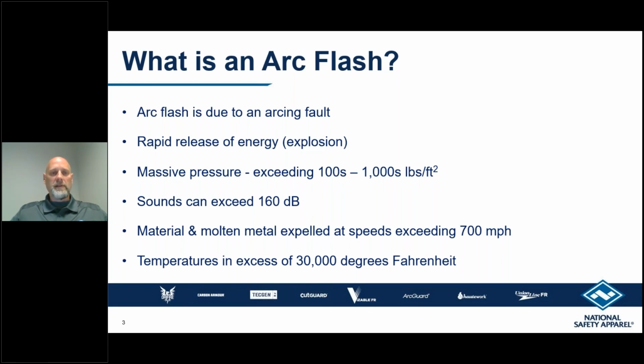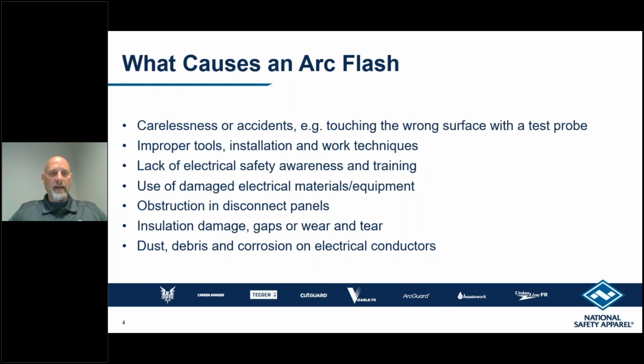It's a rapid release of energy, like a bomb going off, with a massive pressure release and a concussive wave. It can blow out eardrums and throw people across a room into a cinder block wall. Metal components in the electrical system get expelled at speeds up to 700 miles per hour. It vaporizes copper - temperatures reach 30,000 degrees Fahrenheit, far exceeding the surface of the sun. It's a very dynamic, bad situation if somebody draws their unlucky straw that day.